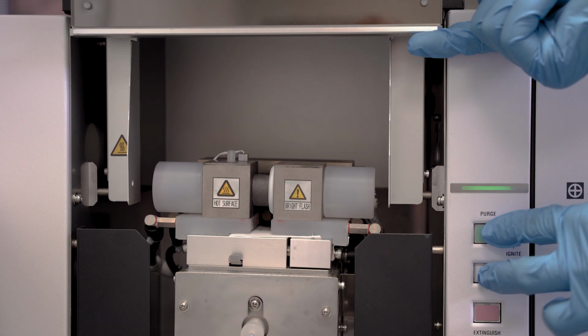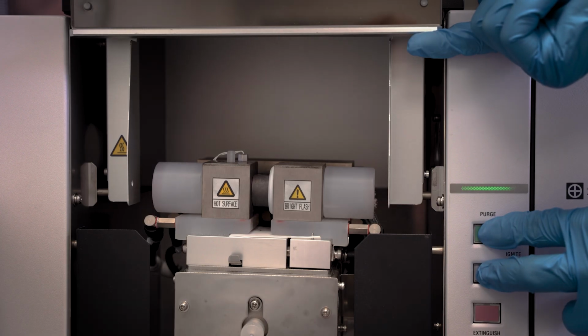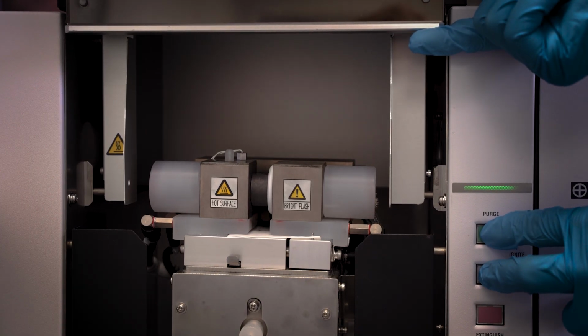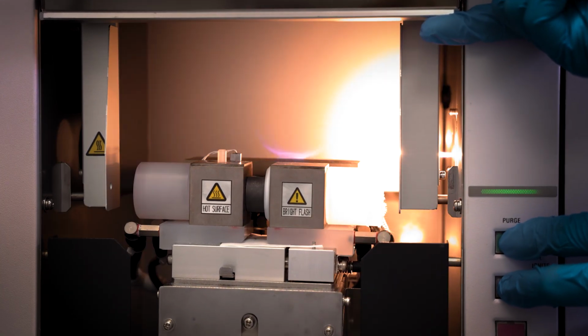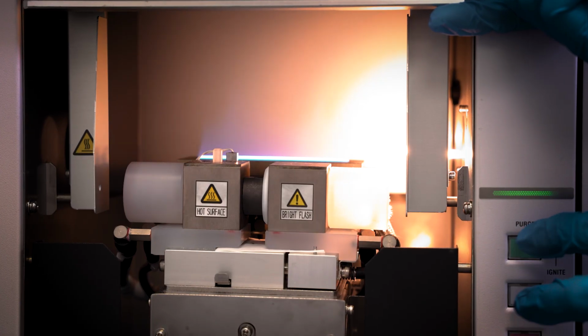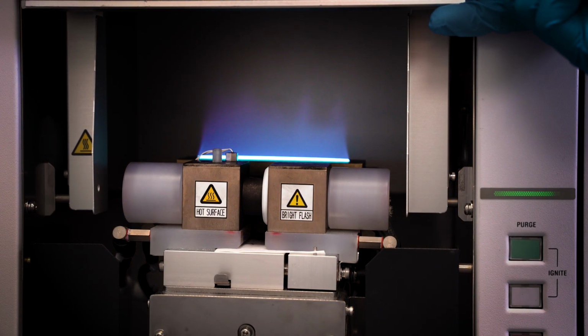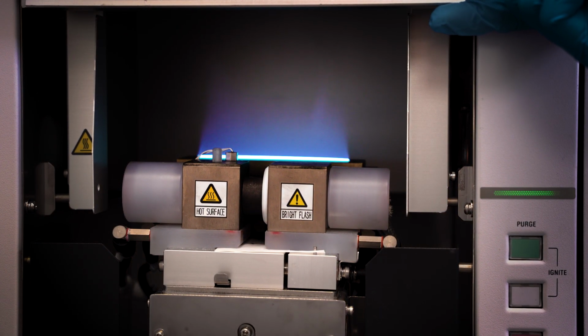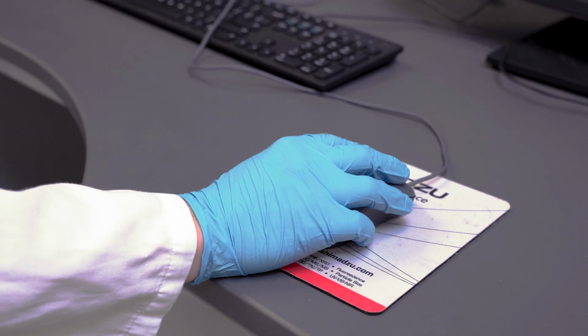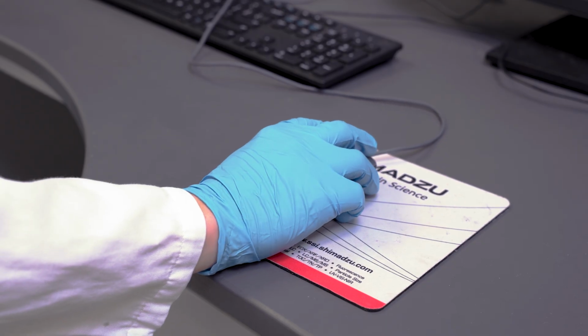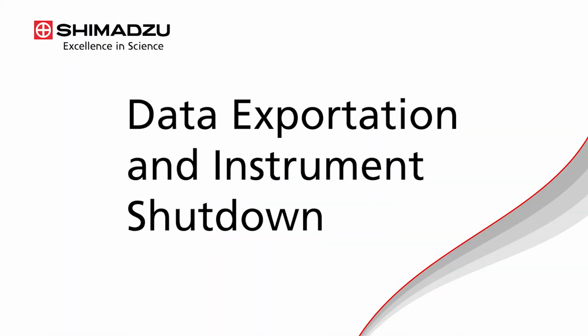At this point, you may turn on the flame by pushing both the purge and ignite buttons at the same time. Please note that it is common for it to fail the first time if the instrument hasn't been turned on in a while. If it does not ignite, click No and retry. Confirm that the flame has been lit. At this point, the instrument is ready to perform analysis.